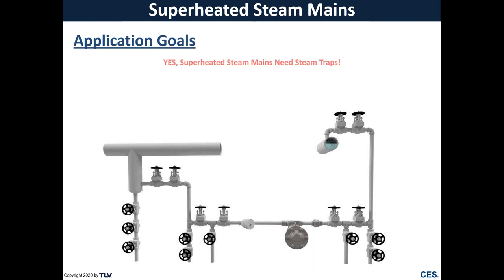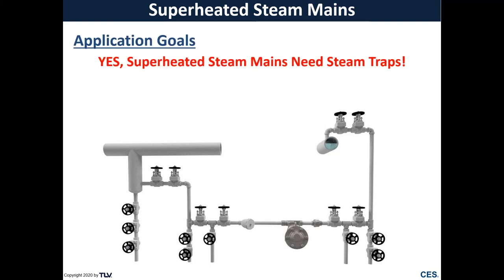So next is steam traps on superheated steam mains. Now you may ask yourself, well, do I really need steam traps on my superheated steam main? The answer here is yes, you still need steam traps on superheated applications. And the reason is you will still see a pretty heavy startup load on initial system startup because that pipe is cold. So you need to be able to handle that condensate on startup.